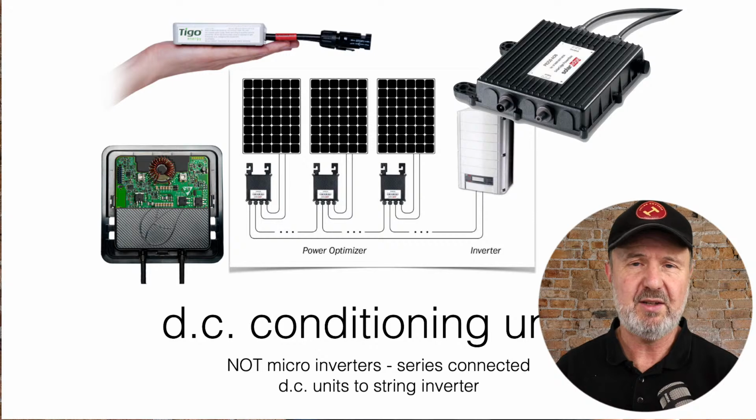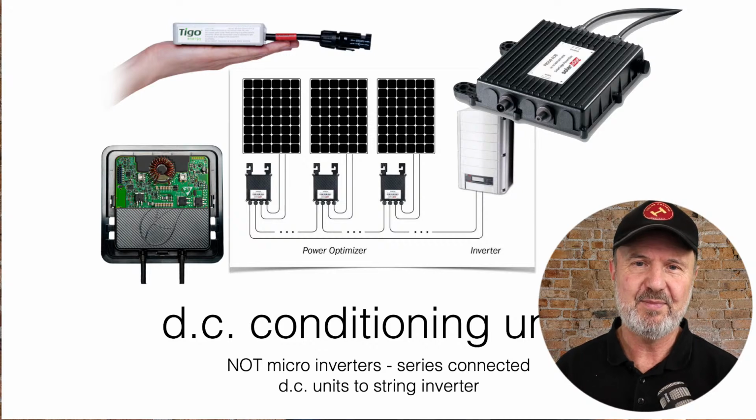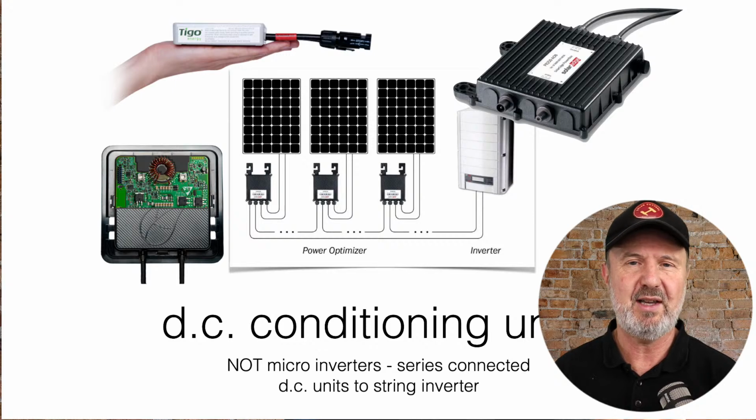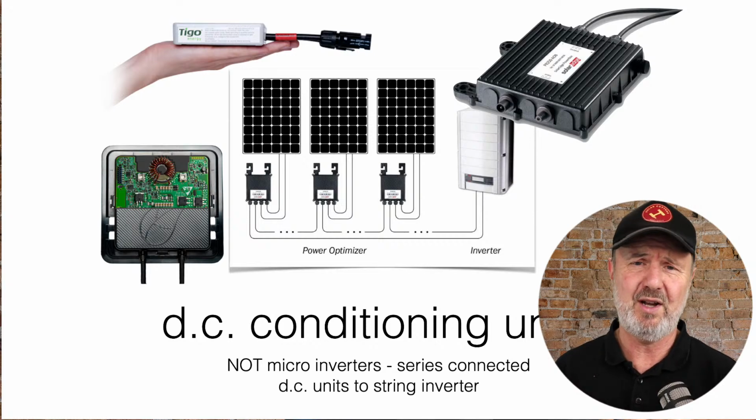We did limit the definition to 350 watts. And back in 2014, that seemed like plenty, but what do you know, panels have got bigger and bigger and bigger. So back then, panels were around the 150 to 180 watt mark. Now they're 300 plus, 400 plus. Jesus, there's 500 watt panels out there now. So that's one of the things that's being revised is the definition of a DCU and what the maximum power of it is without having to have individual isolation on each one.